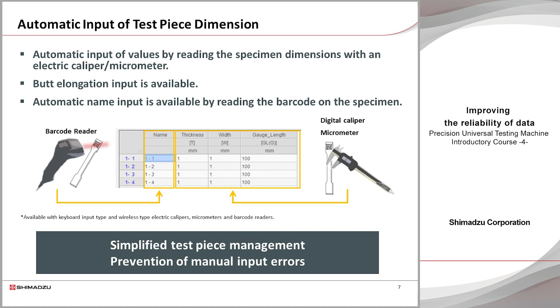Secondly, an automatic dimension input function is introduced. This function automatically enters the dimensions of the test piece. When the dimensions of the test piece are measured with a digital caliper or micrometer connected to the interface, the dimensions are automatically entered. This allows work to be carried out without manual input of the values, thereby eliminating the possibility of incorrect dimensions being entered. A barcode reader can also be used to read the sample number from a QR code attached to the sample and automatically add it to the test piece name entered in Trapezium.